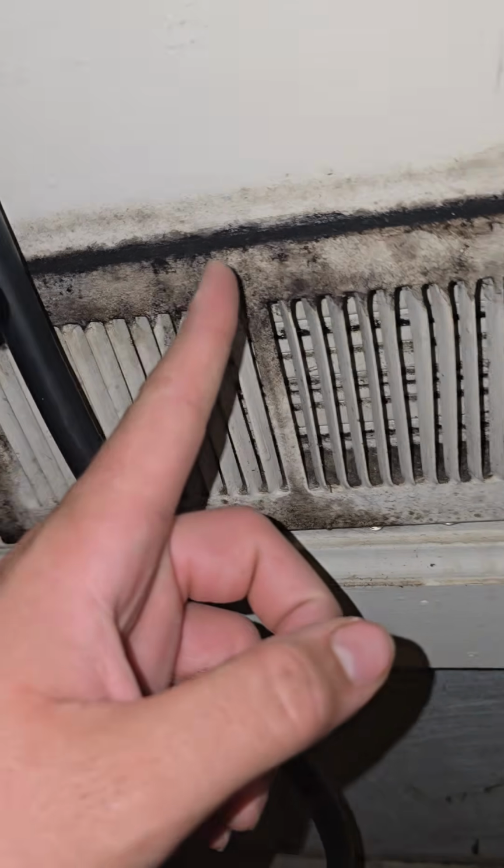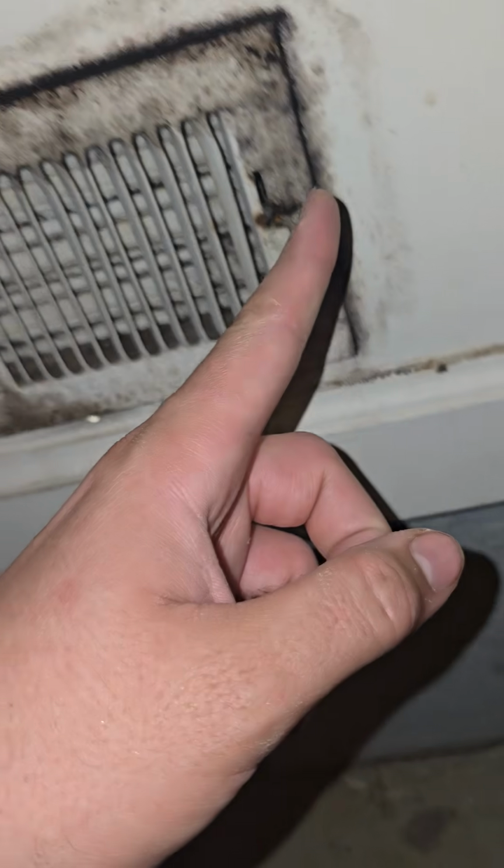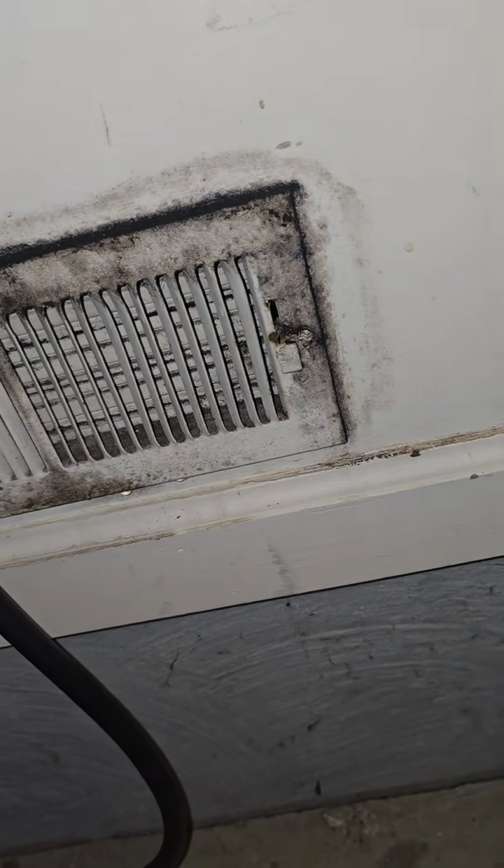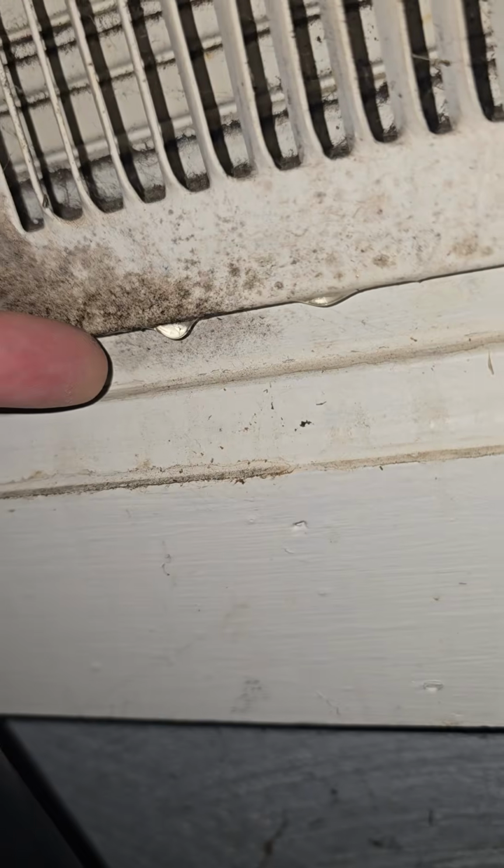Why does mold occur around some air vents? Well, it's usually condensation, and we see some water here, and this is from condensation, but what is causing the condensation here?